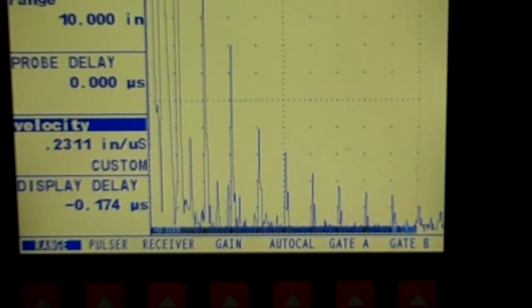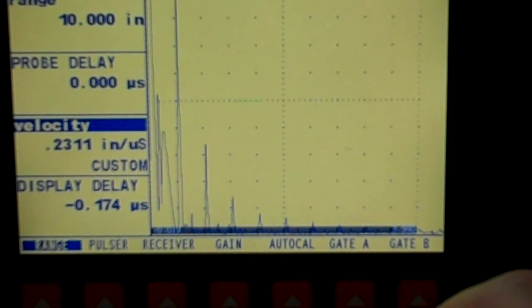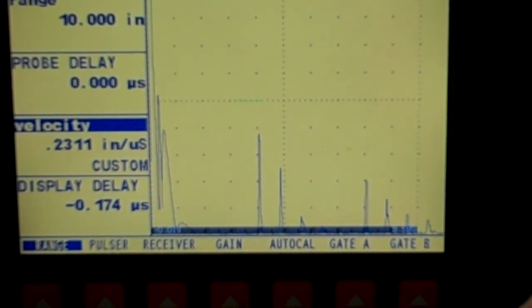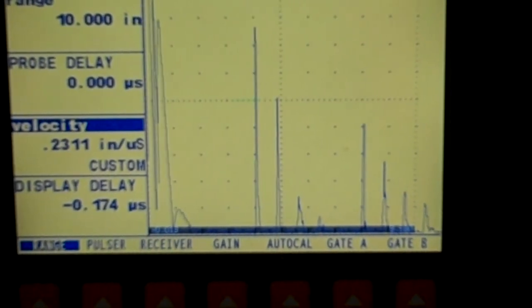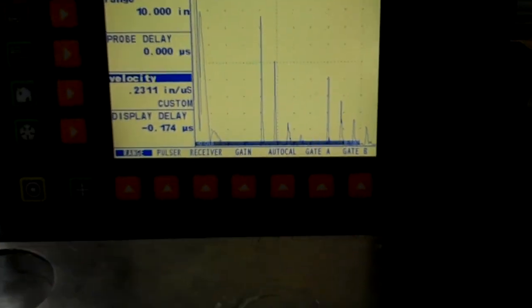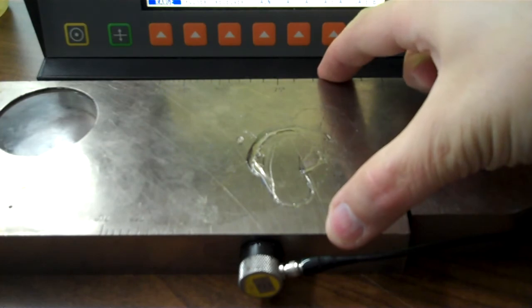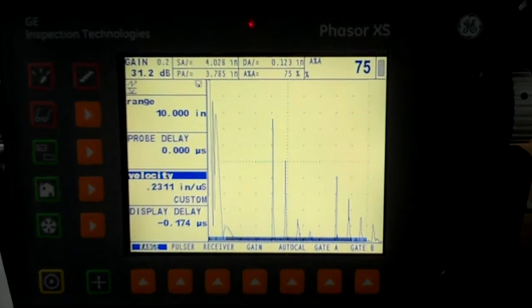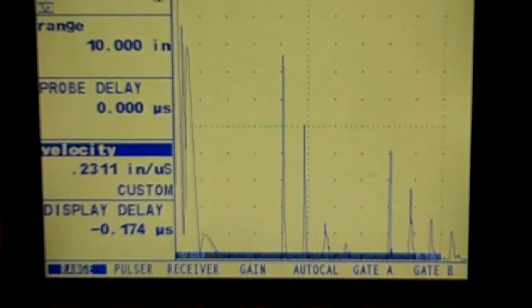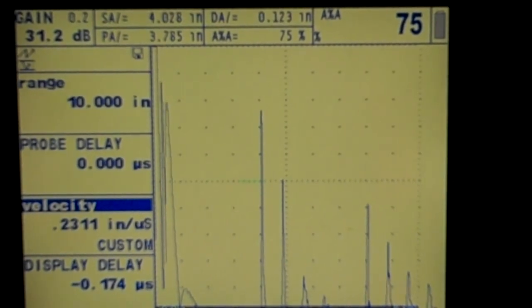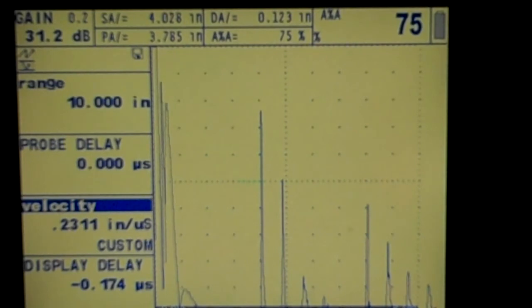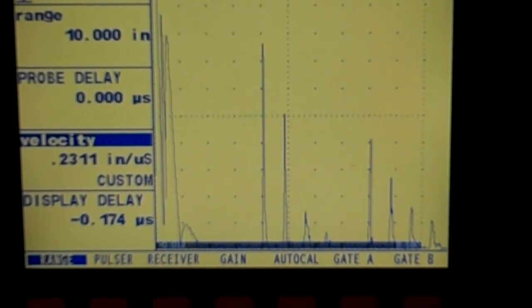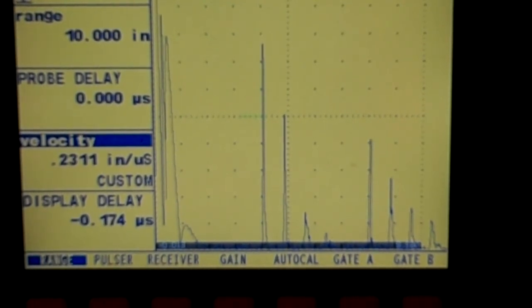So your question for this lab would be, if that's a 10 inch range, how thick is this right here? Remember, this is a 10 inch range. Let me back out so you can see where we're at. We're just on the side of the IIW block shooting this way. So that's a specific thickness. And according to the ultrasonic scope, how thick is that piece? Now remember, each one of those screen divisions represents 1 inch. So that would be your first inch right there. That should give it away. I'll give you a second to look at that. Alright, so you should have it now.